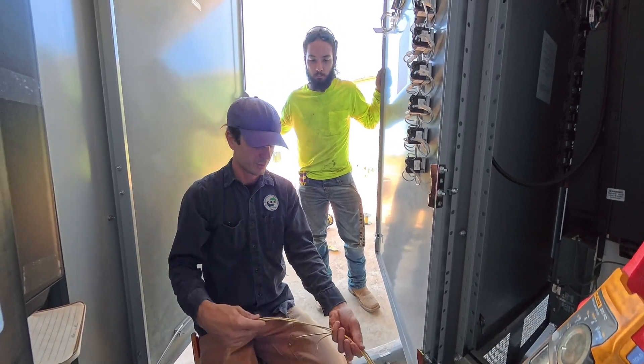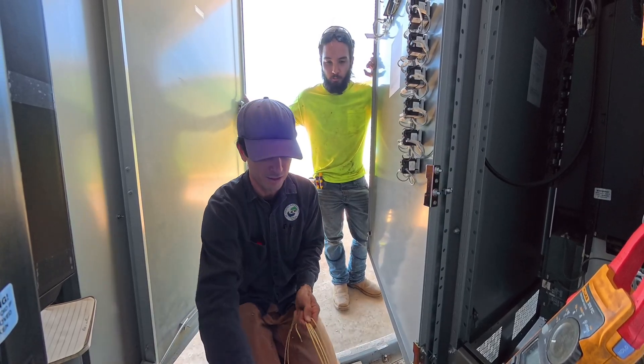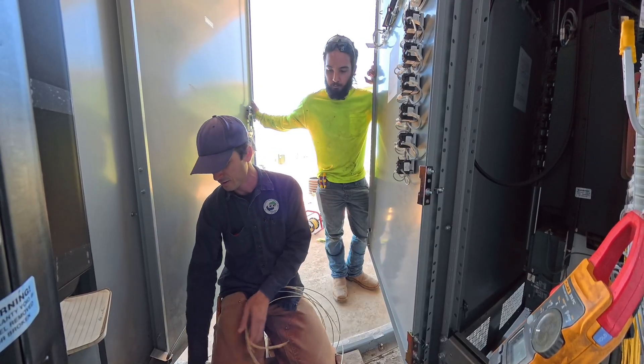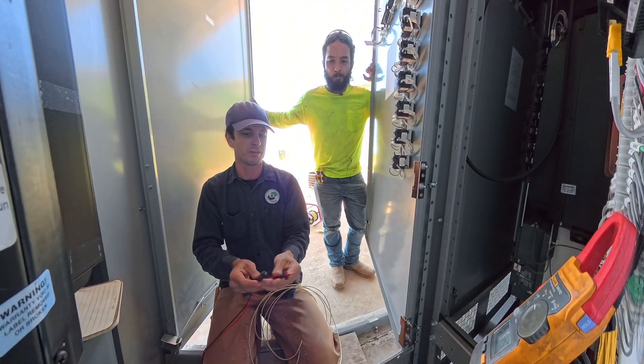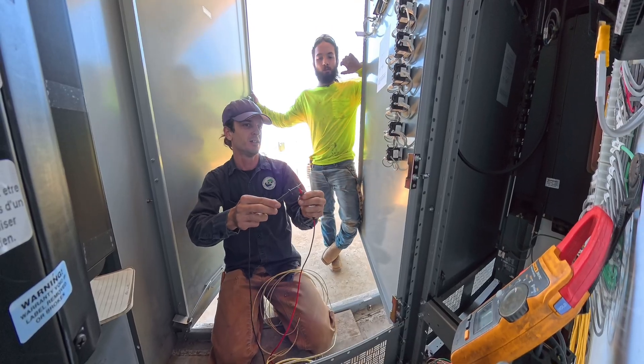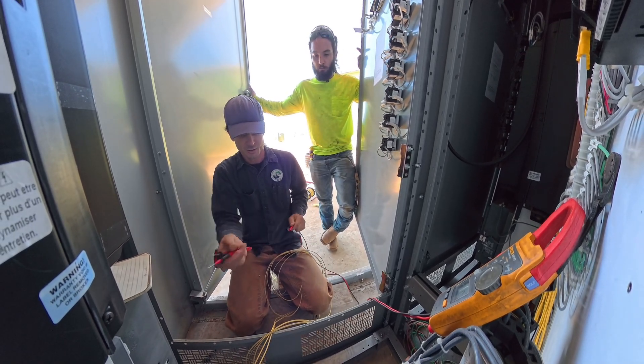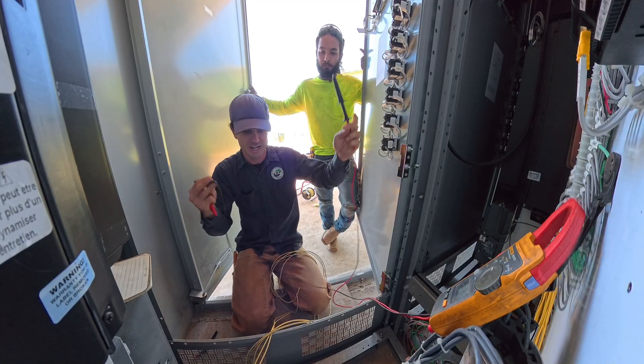The way this works is we need to find out which of these wires is which, because we just pulled them all in and they're all the same color. We'll put them on the outside of the container. We've got five wires and five labels, and on the other end there are five wires and five labels. We've got our meter in continuity mode — the little ohm symbol — which just tells us if something is touching or not. We have a system already in place we can use: the equipment grounds that run throughout this whole place, and everything is de-energized.